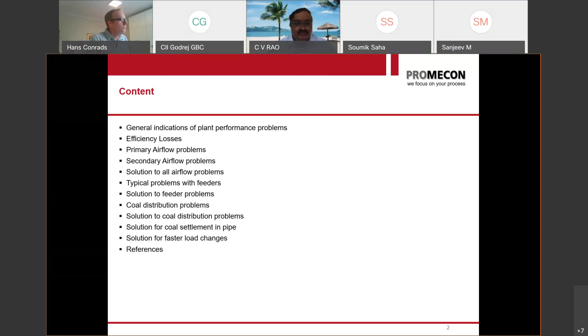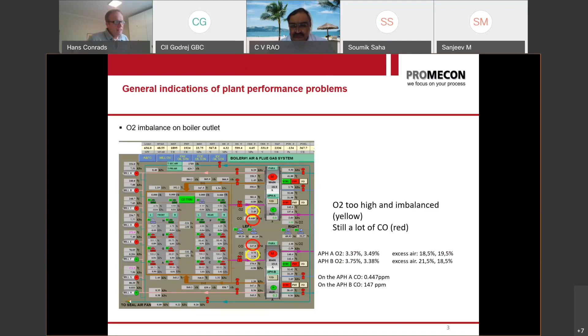When you start at the air heater, you can usually see an imbalance in O2 from the left side to the right side. I have rarely seen an air heater that is really balanced. And the reason for the imbalance that you can see is the maldistribution of airflow in the boiler and the maldistribution of fuel flow in the boiler. So these are 2 things that are the main reasons for that. And the first indication is an imbalance of O2. When I see that, I usually go on to see the superheater section.